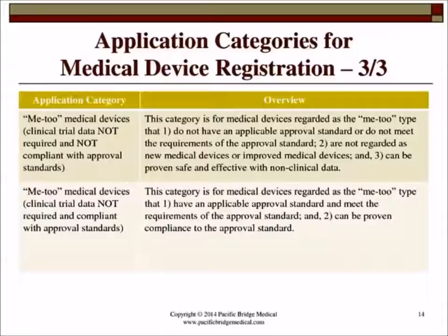So on the Me Too category here, the first one, GCP clinical trial data is not needed to prove safety and efficacy, but in the application documents for the Me Too category here, substantial equivalence to the predicate device in Japan must be clearly shown. For Me Too medical devices, clinical trial data is not required, and compliance with the approval standards, as you can see. And again, GCP clinical trial data is not needed to prove the safety and efficacy.